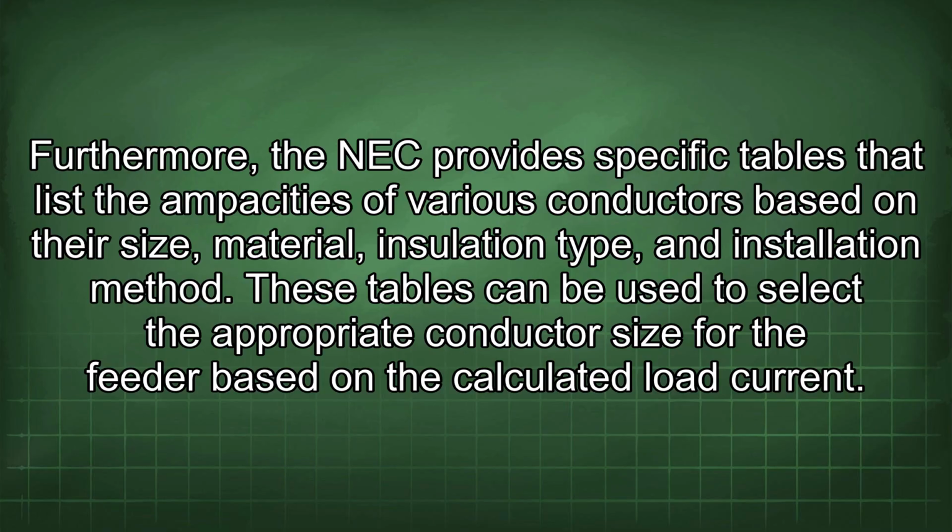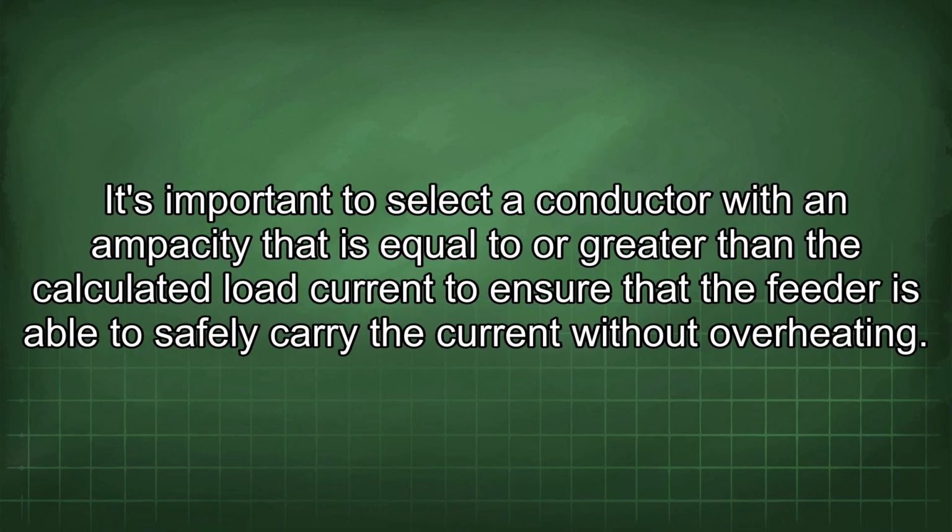These tables can be used to select the appropriate conductor size for the feeder based on the calculated load current. It's important to select a conductor with an ampacity that is equal to or greater than the calculated load current to ensure that the feeder is able to safely carry the current without overheating.